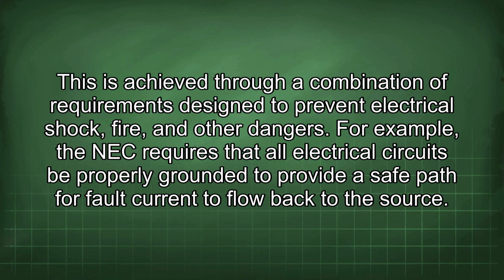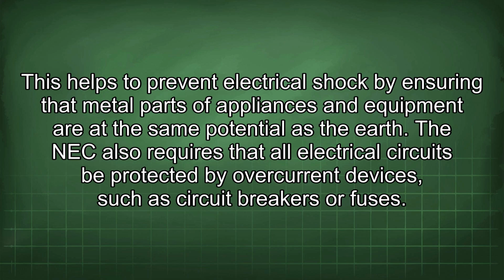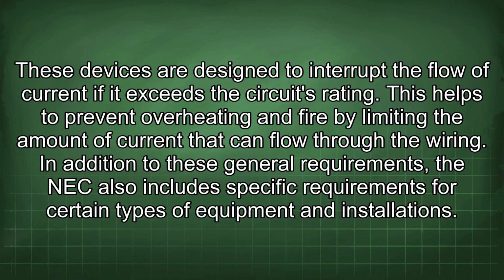For example, the NEC requires that all electrical circuits be properly grounded to provide a safe path for fault current to flow back to the source. This helps to prevent electrical shock by ensuring that metal parts of appliances and equipment are at the same potential as the earth. The NEC also requires that all electrical circuits be protected by overcurrent devices, such as circuit breakers or fuses. These devices are designed to interrupt the flow of current if it exceeds the circuit's rating. This helps to prevent overheating and fire by limiting the amount of current that can flow through the wiring.